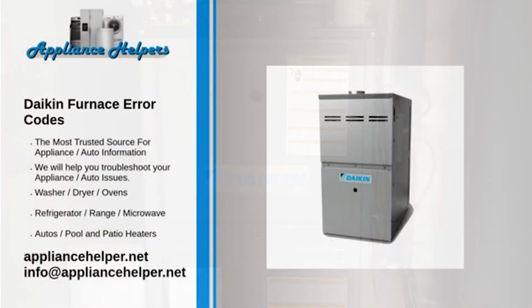If you're looking for help fixing your Daikin furnace, look no further. Our comprehensive Daikin Furnace error code guide will explain common issues, provide tips, and show you how to read your model's error codes. Code: 1 LED flash that stays on continuously. Problem: no signal from the thermostat. Fix: turn off the unit's power and check connections.